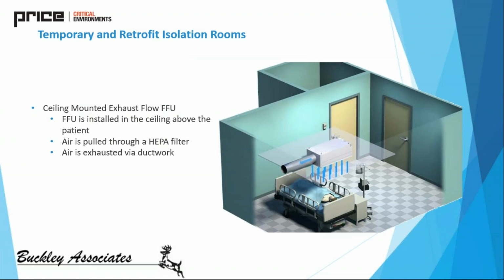Each one of these units, like I said, comes in different configurations. This is how you're pretty much going to see it all of the time. The ceiling mounted exhaust fan filter is probably what's going to be used in a more permanent application. Whether we're talking about new builds or temporary builds, this is where you're going to see it. The fan filter unit is simply installed in the ceiling above the patient, where the air is pulled directly up, filtered, and then either thrown into exhaust or return air ductwork.